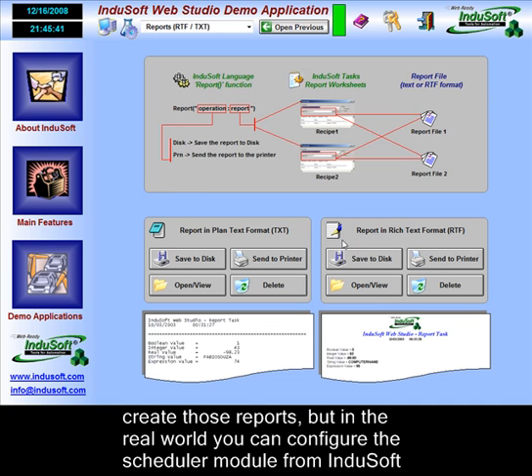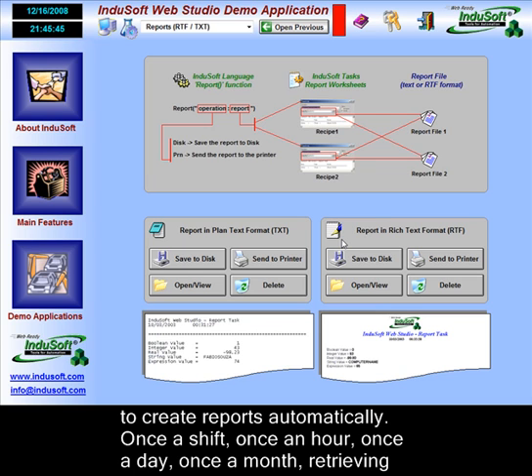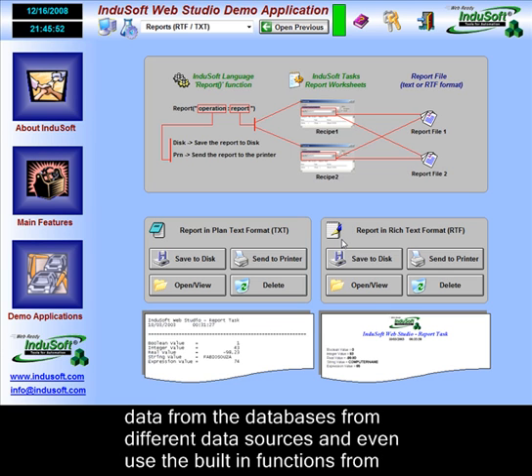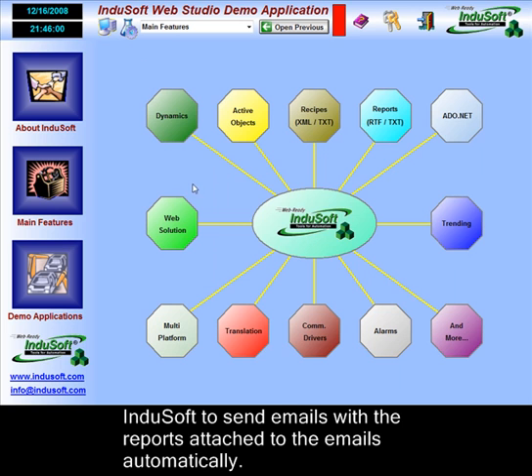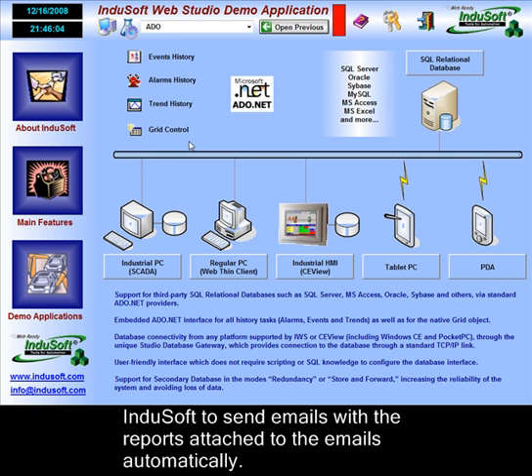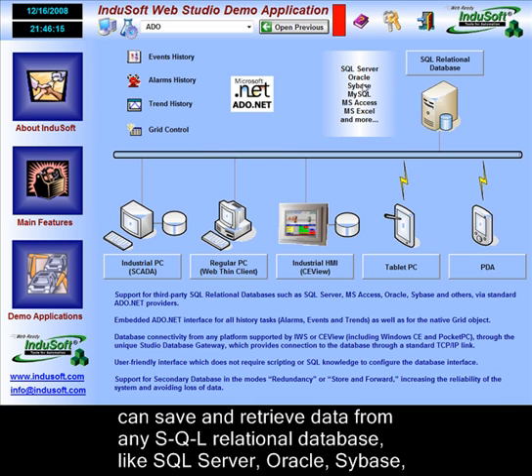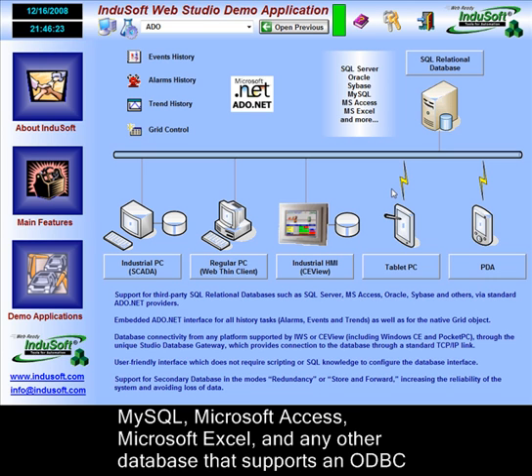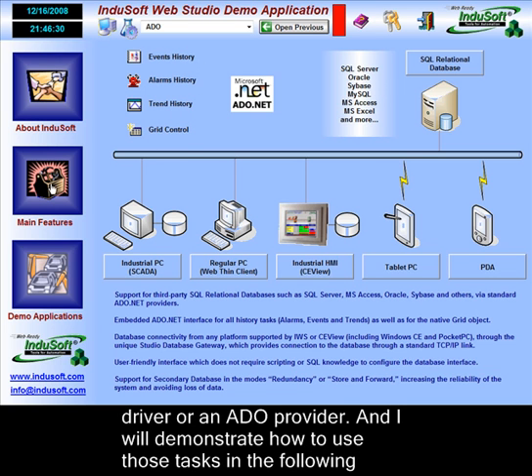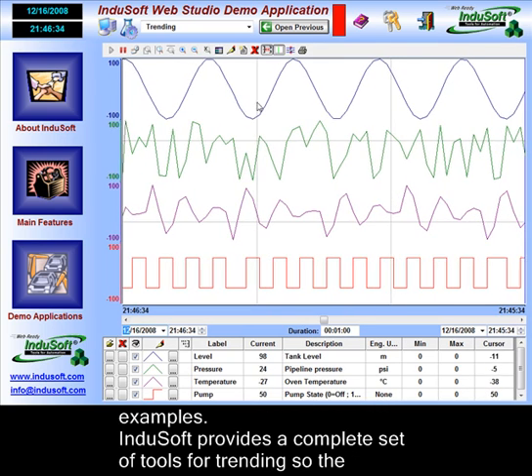In the real world, you can configure the scheduler module from Indusoft to create reports automatically — for instance, once a shift, once an hour, once a day, or once a month — retrieving data from databases and different data sources, and even use the built-in functions from Indusoft to send emails with the reports attached automatically. All of the history tasks from Indusoft — like events history, alarm history, and trend history — can save and retrieve data from any SQL relational database, like SQL Server, Oracle, Sybase, MySQL, Microsoft Access, Excel, and any other database that supports an ODBC driver or an ADO provider.